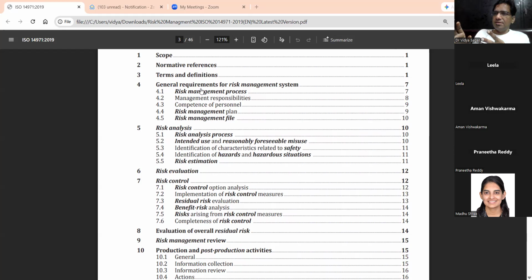They include that because detectability speaks to the effectiveness of your risk controls. Actually, I like that; including detectability is a very good idea. That we call RPN, risk priority number. When you just multiply severity into probability, probability is also called occurrence, and it is just called risk index. But when you add the third parameter, detectability, which is the chance that you are able to detect the risk through your risk controls, meaning their effectiveness, that speaks a lot. Severity into probability into detectability is called the risk priority number, basically used more in the US.